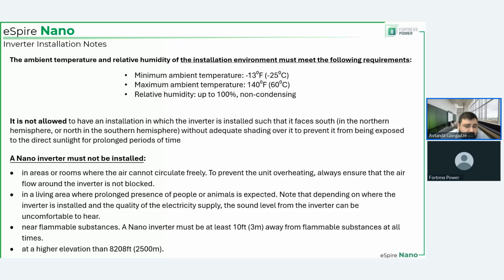If we feel like it's running warmer than we would like on average or median, then we're going to consider derating. But derating is an option. You can go by higher elevations. At some point, we'll also develop a suggested derating percentage per increase of elevation beyond 8,208 feet. That is not ready yet, but we're working on it.